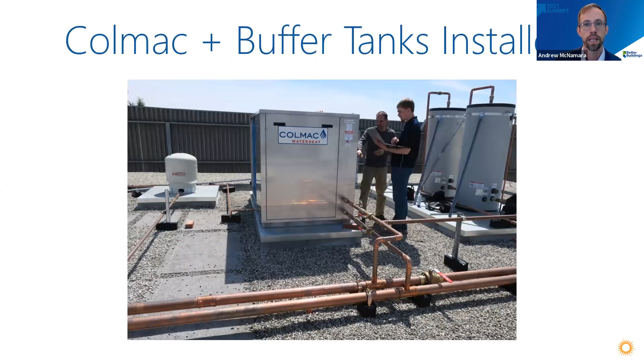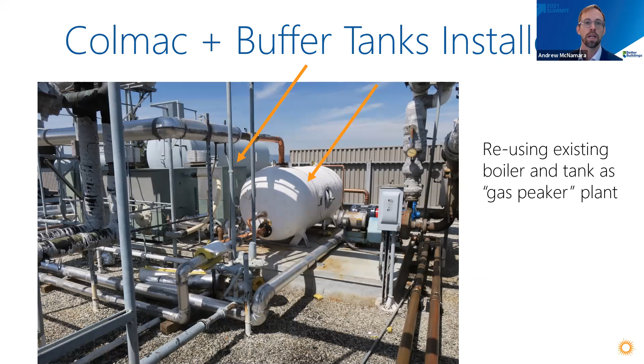On the next slide, this shows the pre-existing boiler and storage tank, which we reused and which act as the gas peaker plant. It provides about 10% of the annual load, but it's there for those rare moments when everyone happens to shower at once, and really helps keep the cost down, because a lot of the capacity you pay for in your water heating system is just there for safety factor. So the safety factor is basically taken care of by these units, and the expensive heat pumps can just cover the base load.